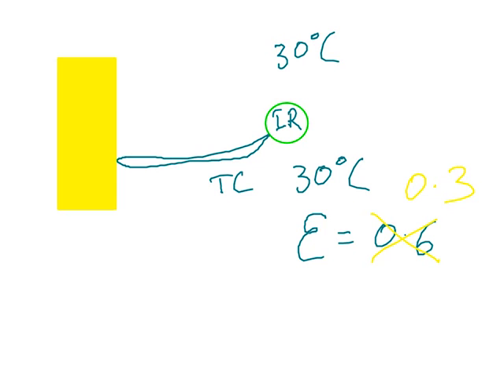If you're measuring a flame, to make sure that there's a flame present, sort of places we do this, if you've got a flare tower on an oil rig, you've got this dirty great big flame, and it's really important to make sure that flame doesn't go out. So what we can do is have an infrared temperature sensor looking at that flame. In fact, we use infrared temperature sensors for flame detectors in boilers as well, to make sure that the flame is lit. So, they're good because they're non-contacting.